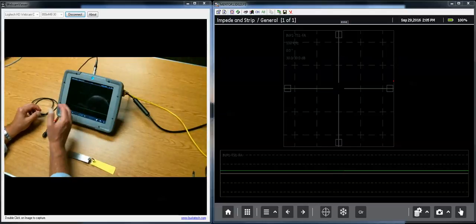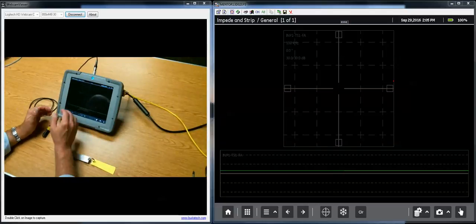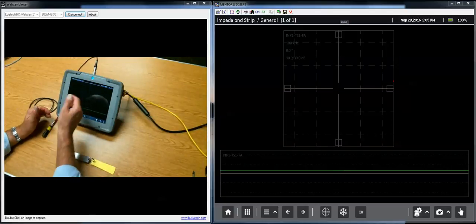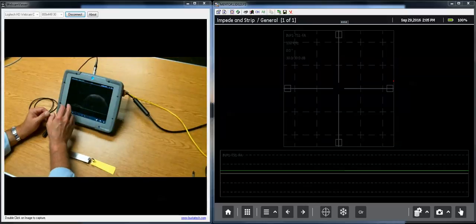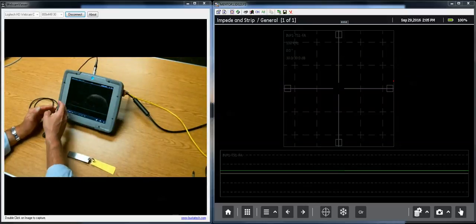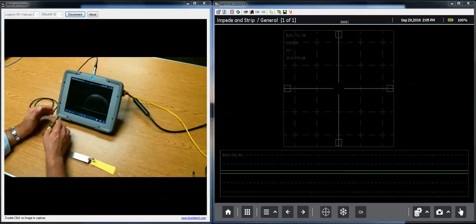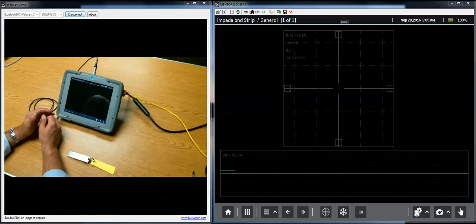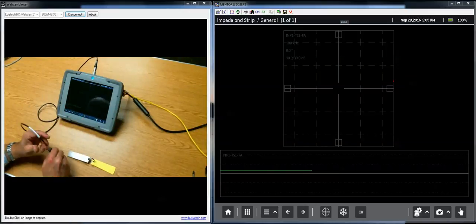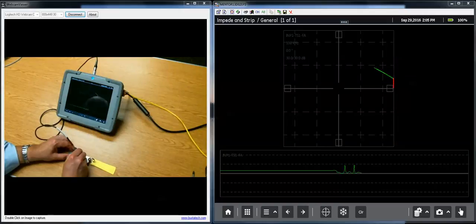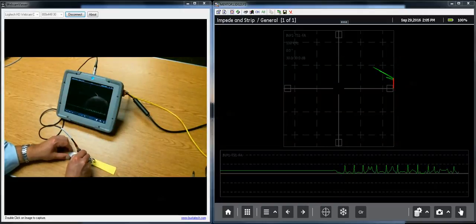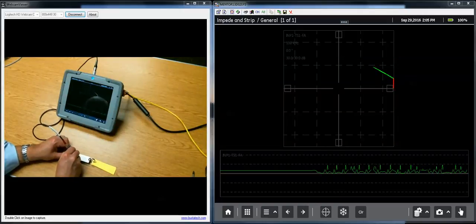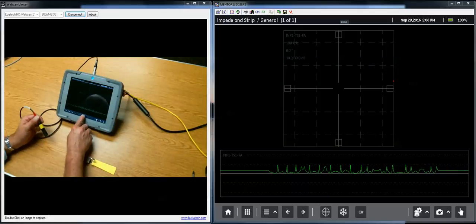The top view is impedance plane, inductance and resistance. The bottom view is amplitude of one axis of that over time. So you notice if I clear it I get a trace that draws in from left to right, and as I run the probe over a notch in a part I get a series of indications.